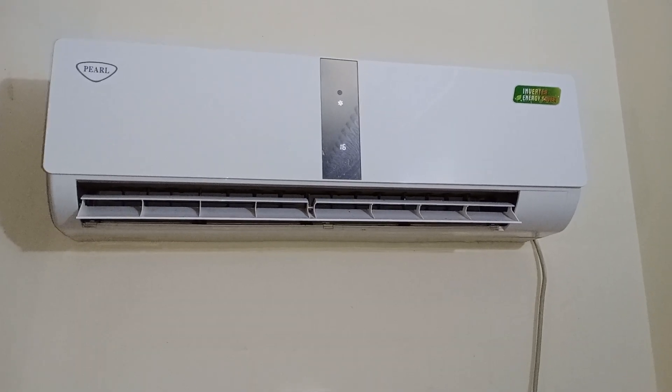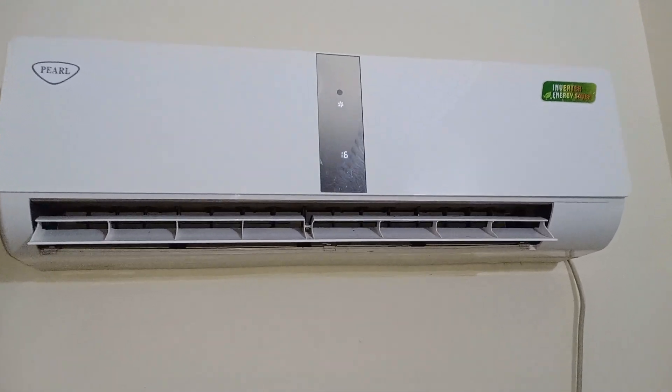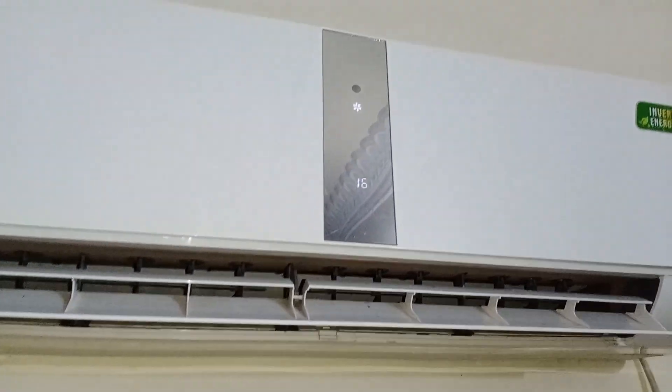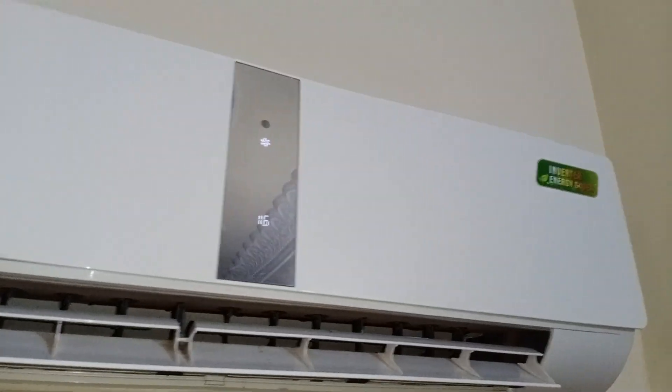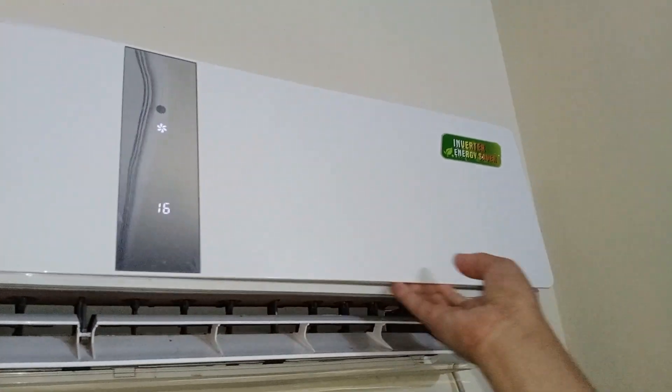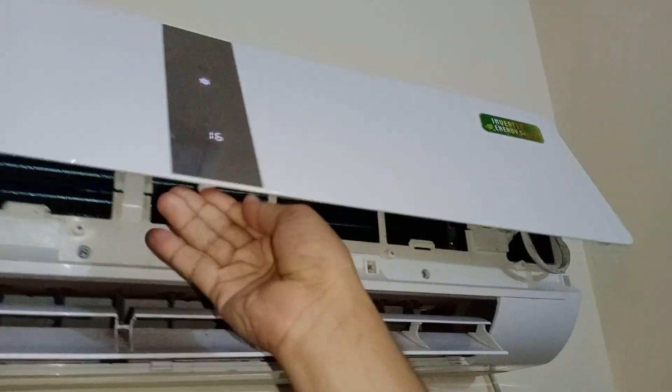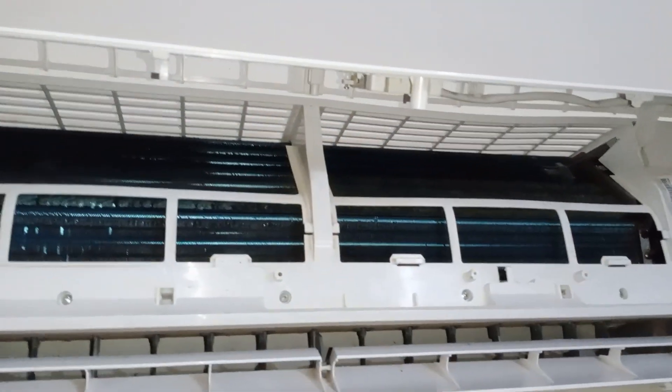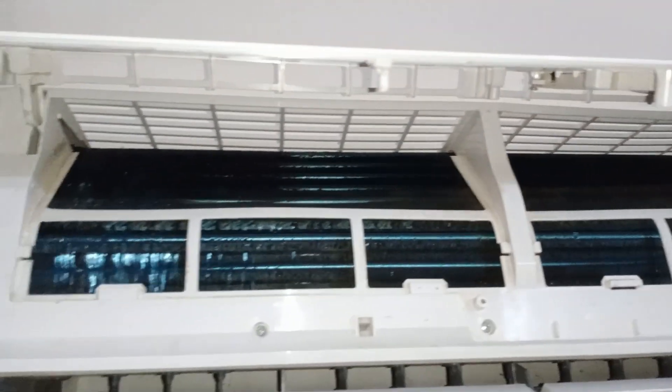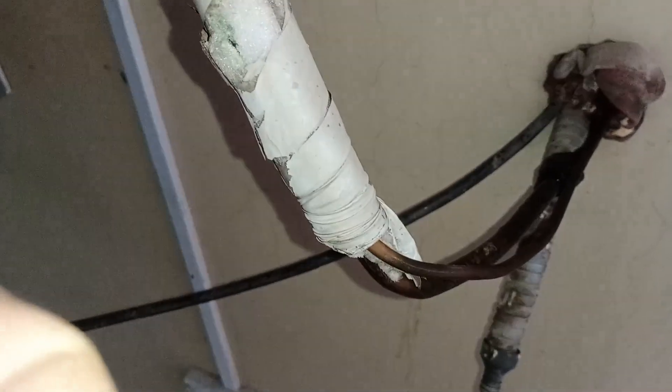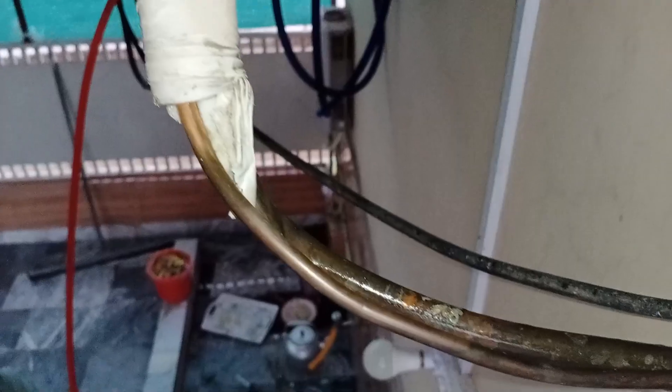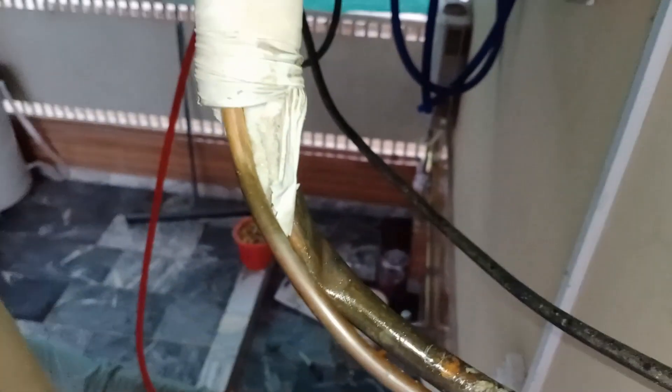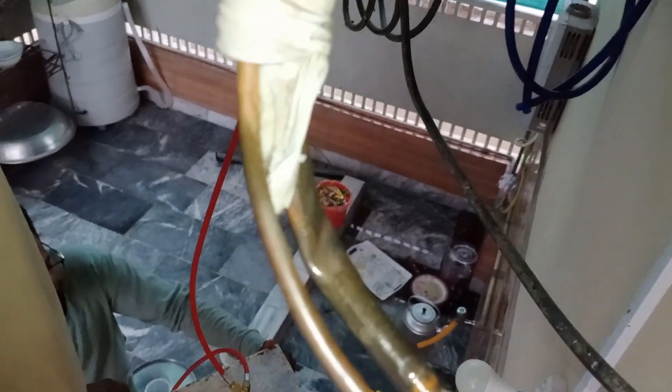This is a Pearl DC inverter air conditioner, and it was also experiencing ice formation on the suction pipe. Initially, I assumed the issue was due to a clogged evaporator, but my assumption was incorrect, as the evaporator was clean. The owner also confirmed that it had been recently serviced. Next, I moved to the outdoor unit for further inspection. Upon checking, I noticed that one of the pipes was bent on one side.